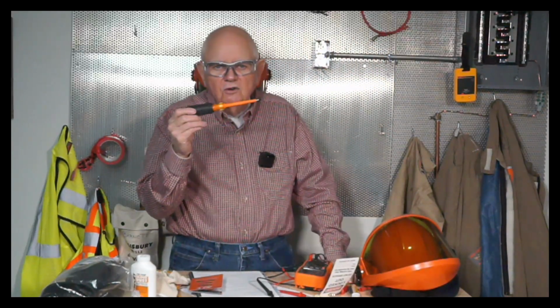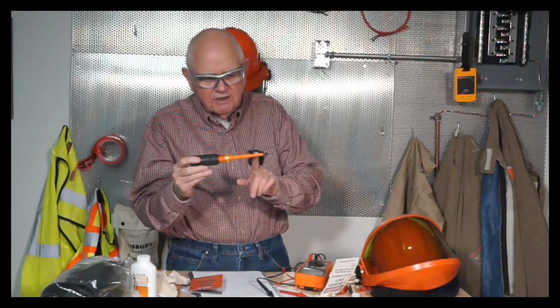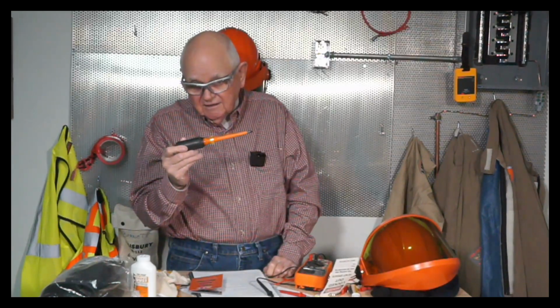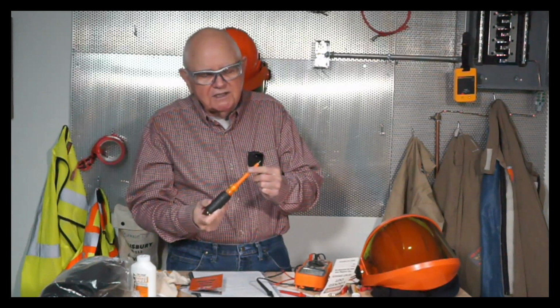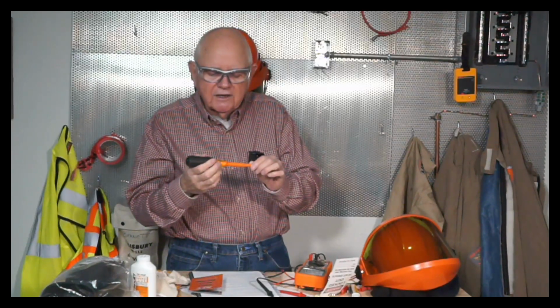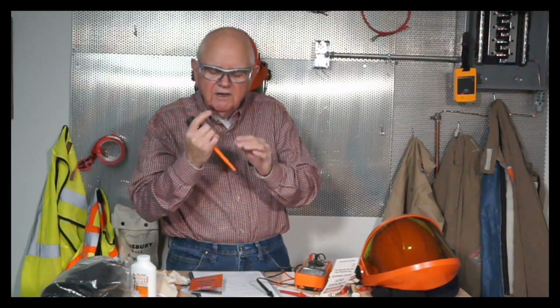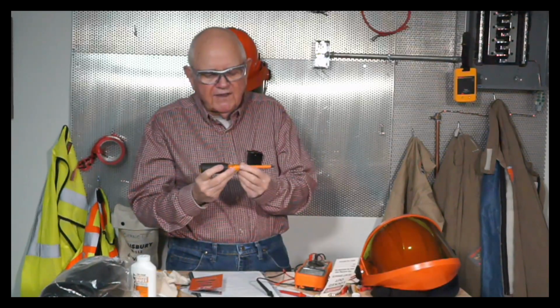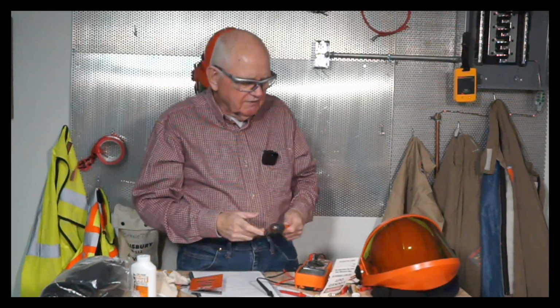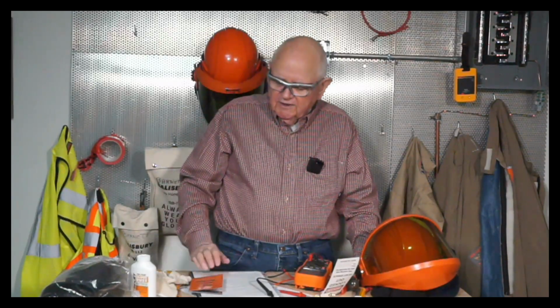Inspect any insulated tools. If I'm going inside that restricted approach boundary, make sure your insulated tool is rated. This one is double insulated, so it has the two little boxes on it. It also has a triangle, one triangle inside of the other one. That tells me it's been tested to 1000 volts. So I do a visual inspection of that as well. Now, once again, I'm moving through this pretty fast. If you need more information, you can watch other Tech Talks, but you want to make sure that you're covering items like this not only in your 3-year refresher, but in your weekly, monthly, whatever it is, toolbox safety talks that you have as well. Some good topics here for the electric shop folks.